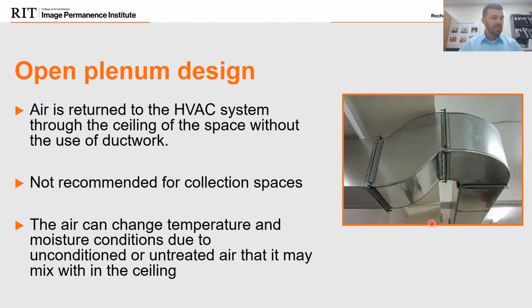One of the last items I want to talk about within your air handling units is open plenum design. The image on your right is the exact opposite of the open plenum design. Open plenum is when your air is returned from your HVAC system right into the ceiling, an open ceiling of the space, without the use of ductwork. So we really don't recommend it for collection spaces. We want to keep that air as contained as possible.